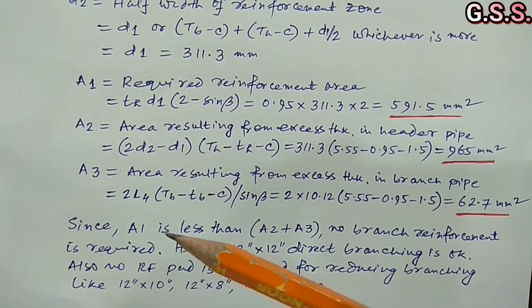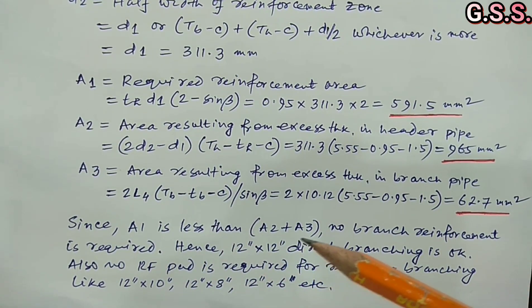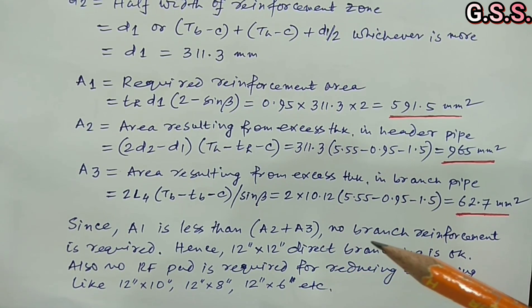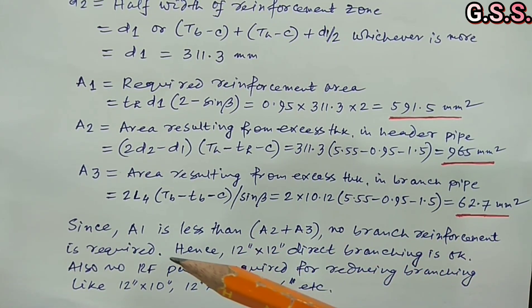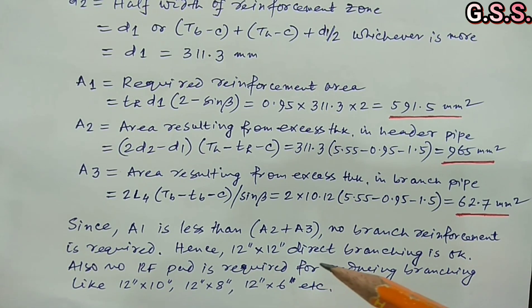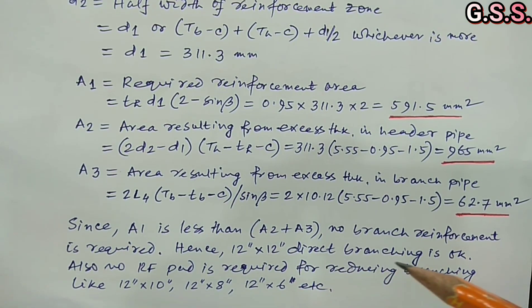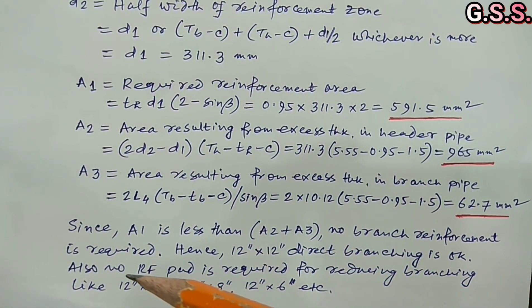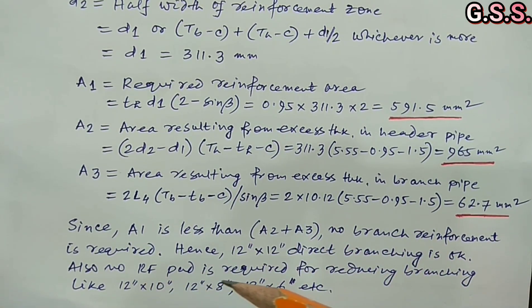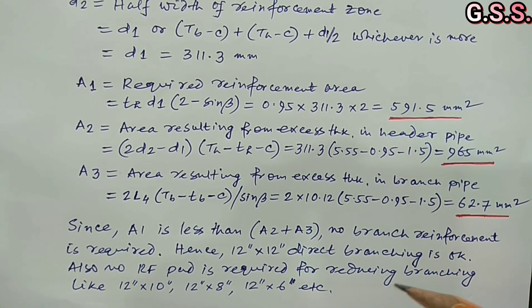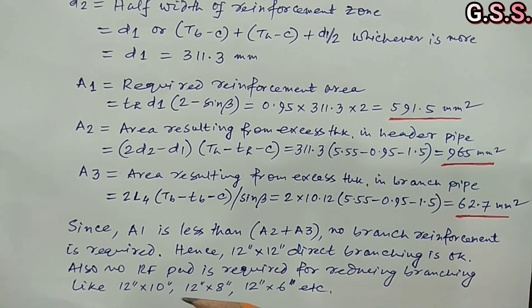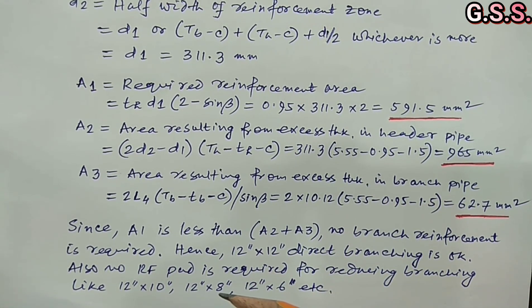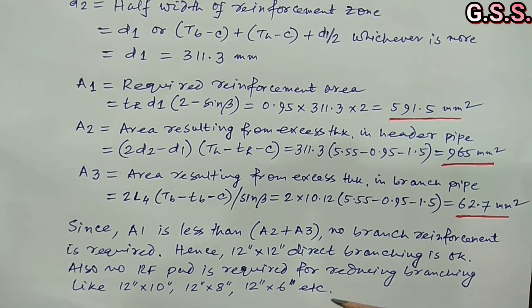Since A1 is less than A2 + A3, no branch reinforcement is required. Hence, 12-inch by 12-inch direct branching is okay. Also, no RF pad is required for reducing branching like 12-inch by 10-inch, 12-inch by 8-inch, 12-inch by 6-inch, etc.